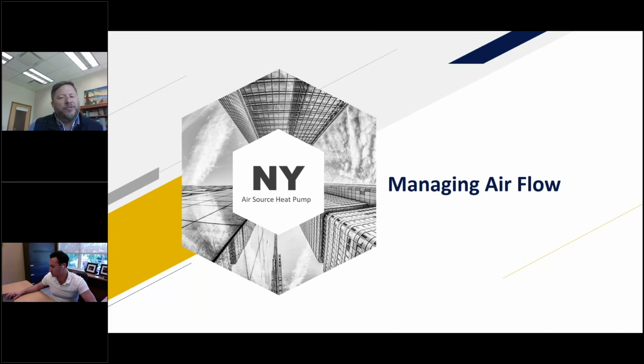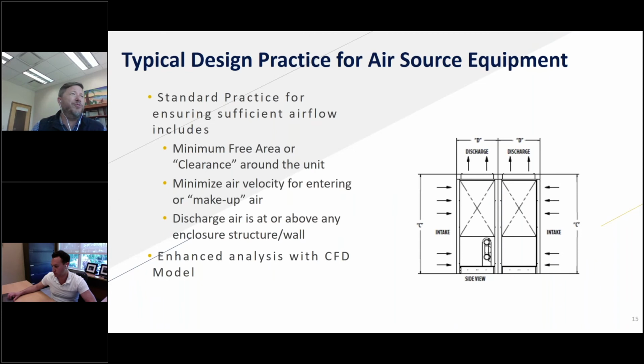So the other part that I talked about was managing airflow. This is a little bit different than heating with traditional technology, where we wouldn't have to worry about this. But when we talk about an air source heat pump, it's really no different than an air-cooled chiller from an airflow perspective. So all the things we typically do as standard practice for ensuring sufficient airflow for a chiller apply to an air source heat pump, especially since it has multiple modes of operation. In the middle of the summer, it's potentially even cooling, so it really is acting as an air-cooled chiller. In the middle of the winter, it's acting as an air source heat pump, so as a heater.